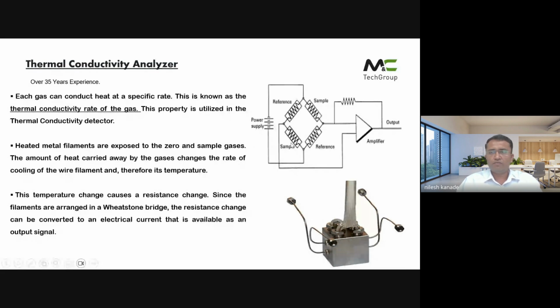There are 4 types of heating elements. Two of them generate constant heat with constant current, and across these two are the reference elements containing the samples. When gas is provided to these reference elements, it takes heat out of the chamber, and the current required to rebuild that heat is proportional to the gas being analyzed.